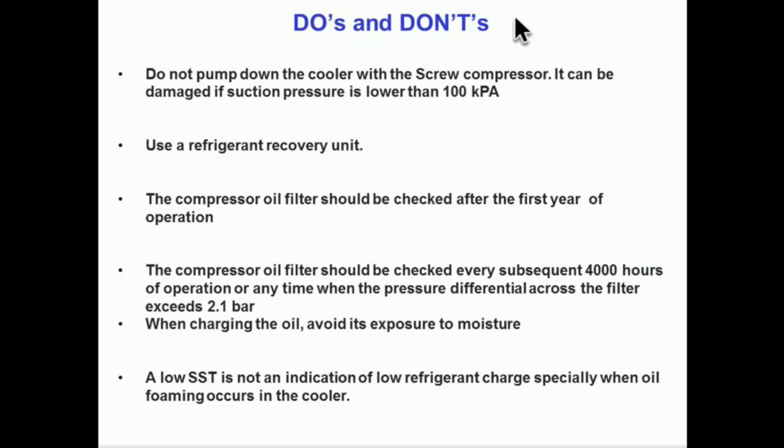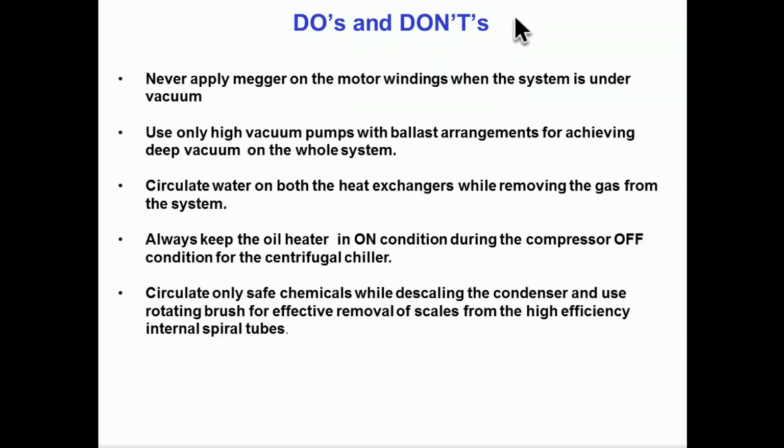A low saturation suction temperature is not necessarily an indication of low refrigerant charge, especially when oil foaming occurs in the cooler. Whenever oil goes into the cooler, oil is a very good insulator. That means it forms on the evaporator tubes, so heat transfer is not going to take place. So when oil is in the system, naturally the saturation suction temperature will be lower. You should not think it is because of any refrigerant metering device problem. Before that, you need to first collect the oil, and only then go into that level.